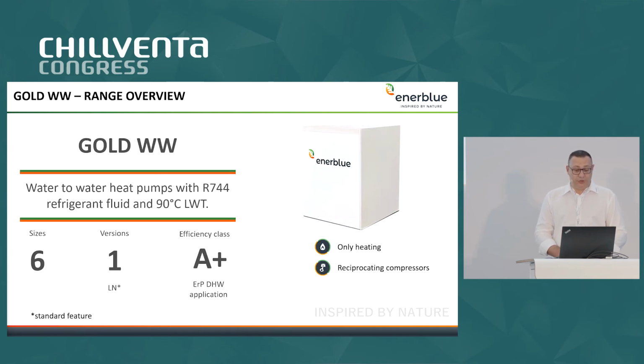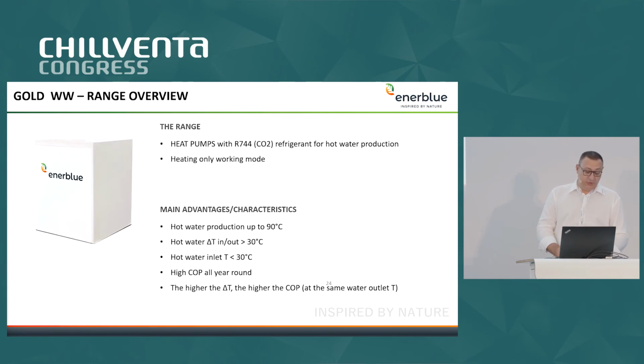The water-to-water version, in this case, the sizes are more or less the same, but we have a water-to-water unit. So 6 sizes. In this case, all the units are already in low noise version. And for all units, for domestic hot water application, we have an A+ class. So the range, also in this case, is heating only working mode. The main characteristics and advantages are more or less the same. So very high leaving water temperature, about 90 degrees. Delta T always bigger than 30 degrees.